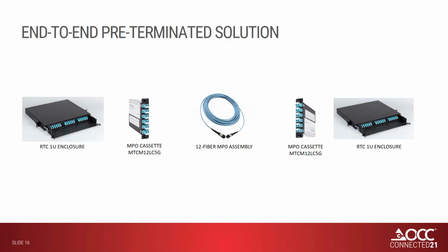Here we have a 12 fiber MPO assembly using our HC cable, which is riser rated. We typically put a pulling eye on one end, so as you install it through a conduit or cable tray, the connector end stays protected. Next in line you have an MPO cassette, factory terminated, with an MPO connector receptacle on the back, fibers inside, and an adapter plate on the outside.